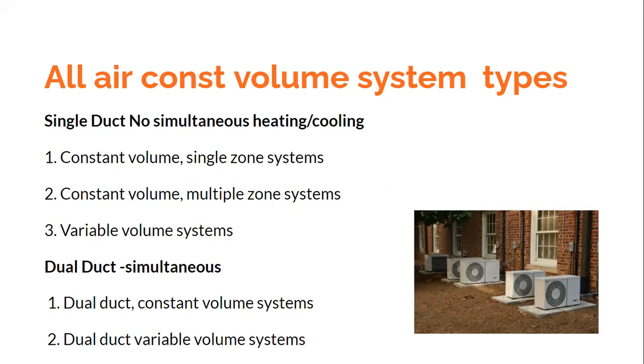Again, depending upon how you maintain the conditions in the rooms to be conditioned, they could be further classified as single zone systems or multiple zone systems. And though in the title it is written constant volume, at times you might require to change the volume, and in that case it could be a variable volume system, catering either to a single zone or multiple zones. As I said, in the dual duct system, you use simultaneously two ducts for supply and two ducts for return, meaning that you can simultaneously heat as well as cool the given space to be conditioned. Again, you can classify the dual duct system further into a constant volume system and a variable volume system. Okay.